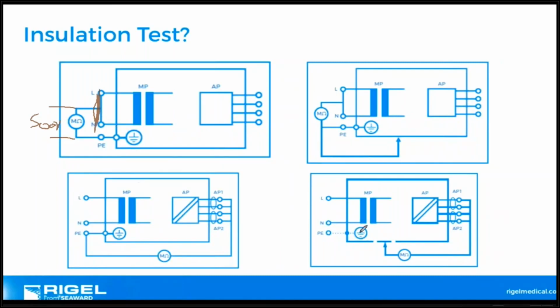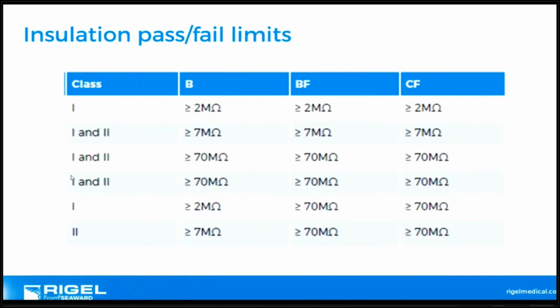And then we have various different permutations of the test. I'm not going to go through them all, but it's not mandatory, and does have different pass-fail thresholds depending on what type of test you're doing and depending on the classification of equipment. But this is a DC test. Remember, AC currents, DC currents. A DC test is just that extra dielectric strength test. Manufacturers of medical equipment will typically suggest an insulation test. I've seen that many times in service manuals. So you need an electrical safety analyzer that's flexible and can incorporate different test scenarios. So having an electrical safety analyzer with an insulation test is definitely handy. Otherwise, you're just going to be tripped up with your preventative maintenance schedules.